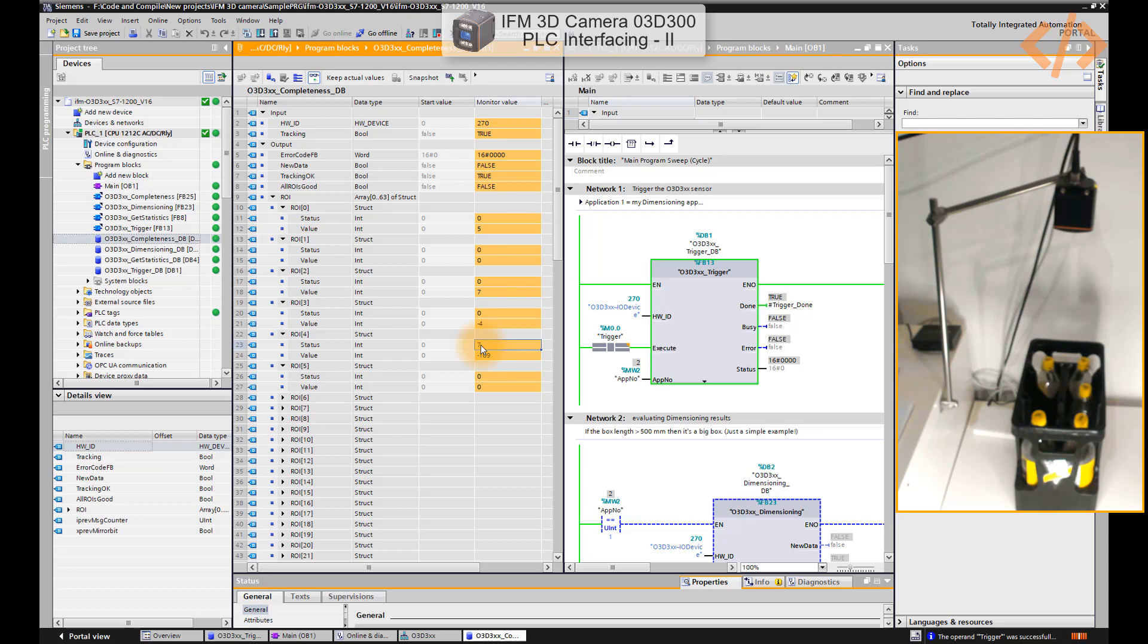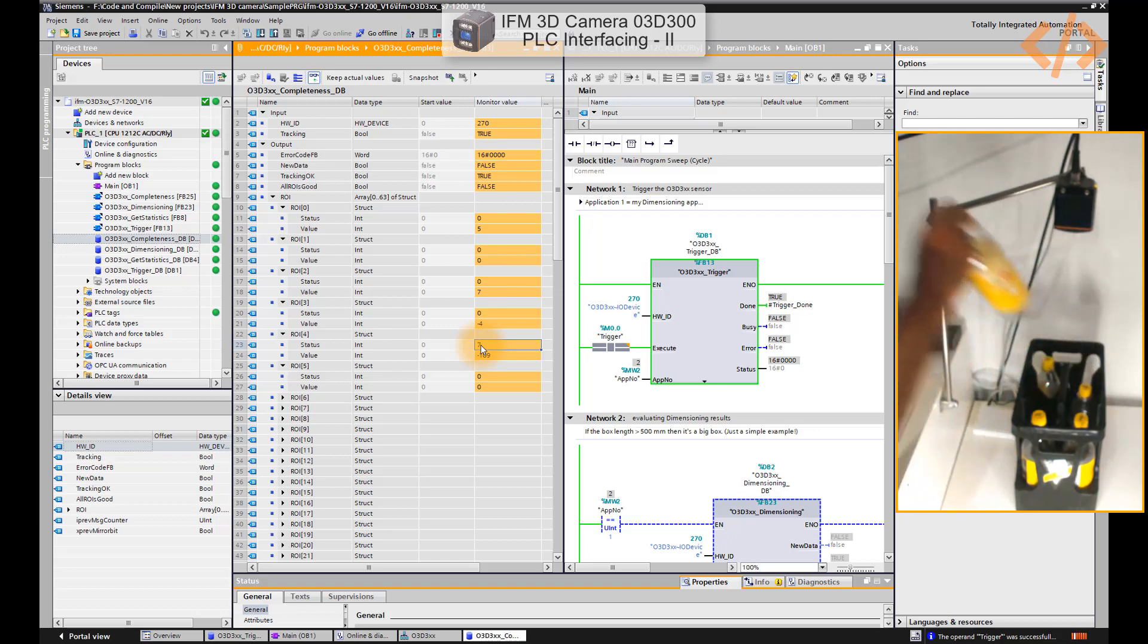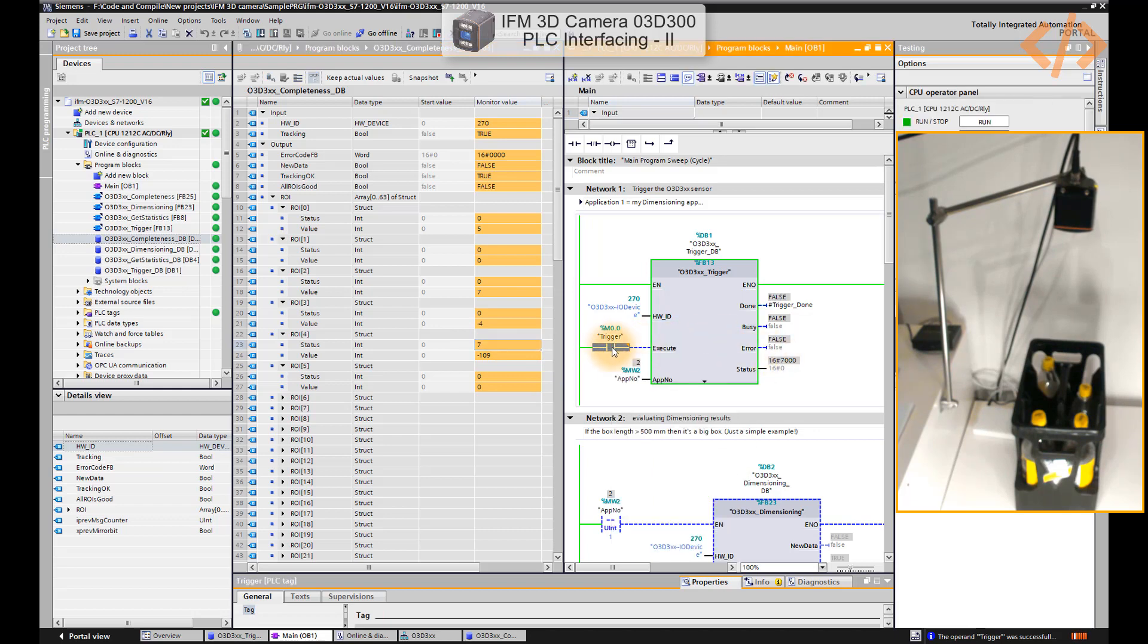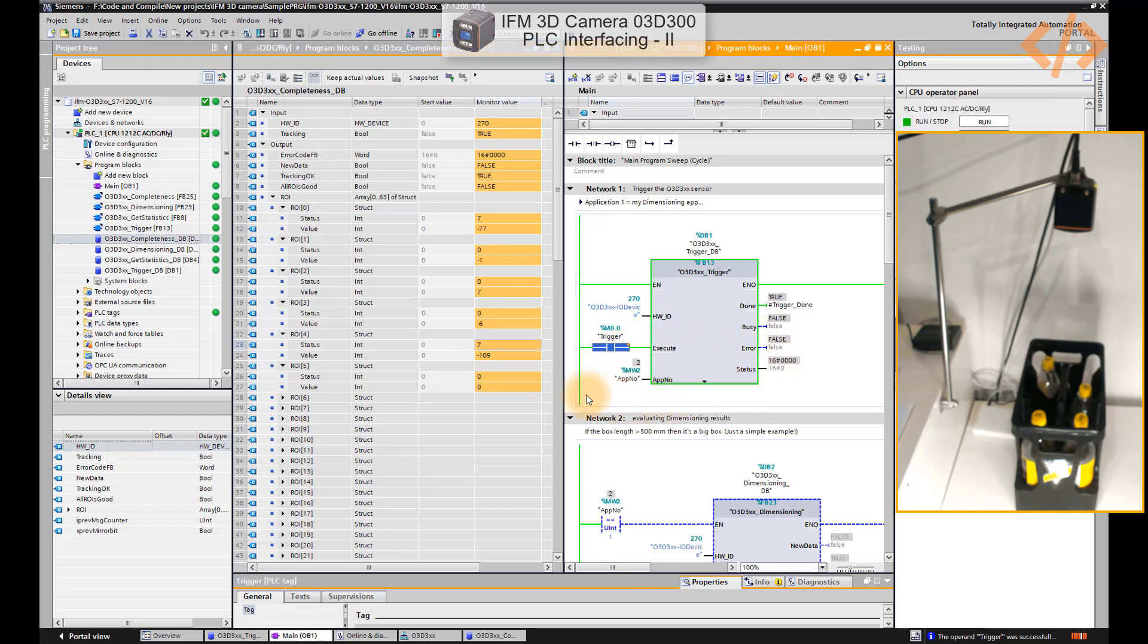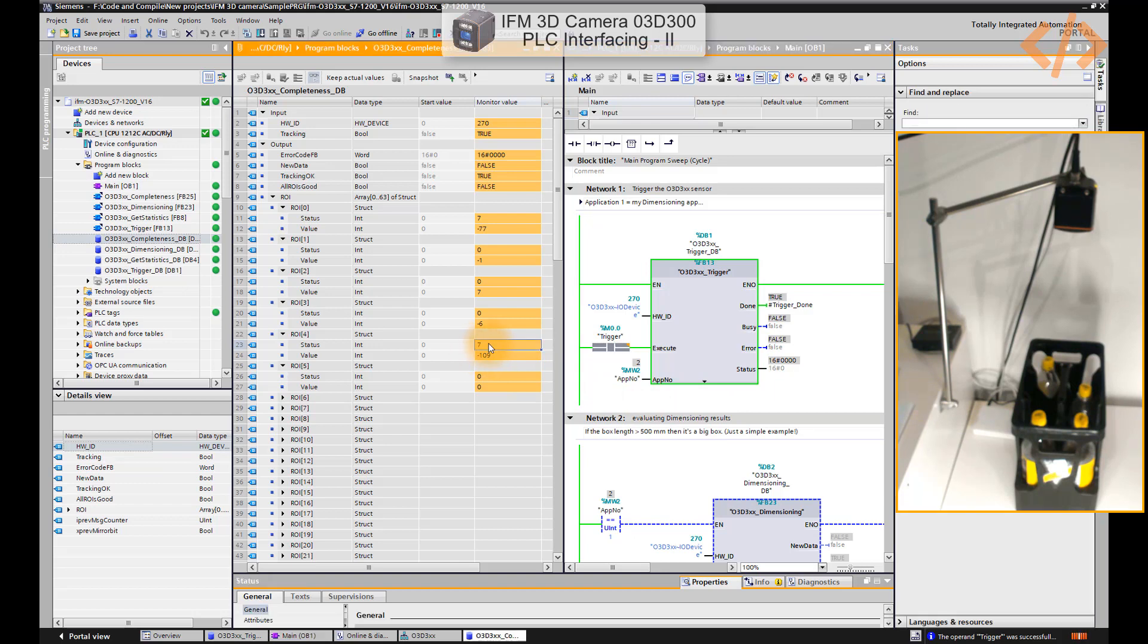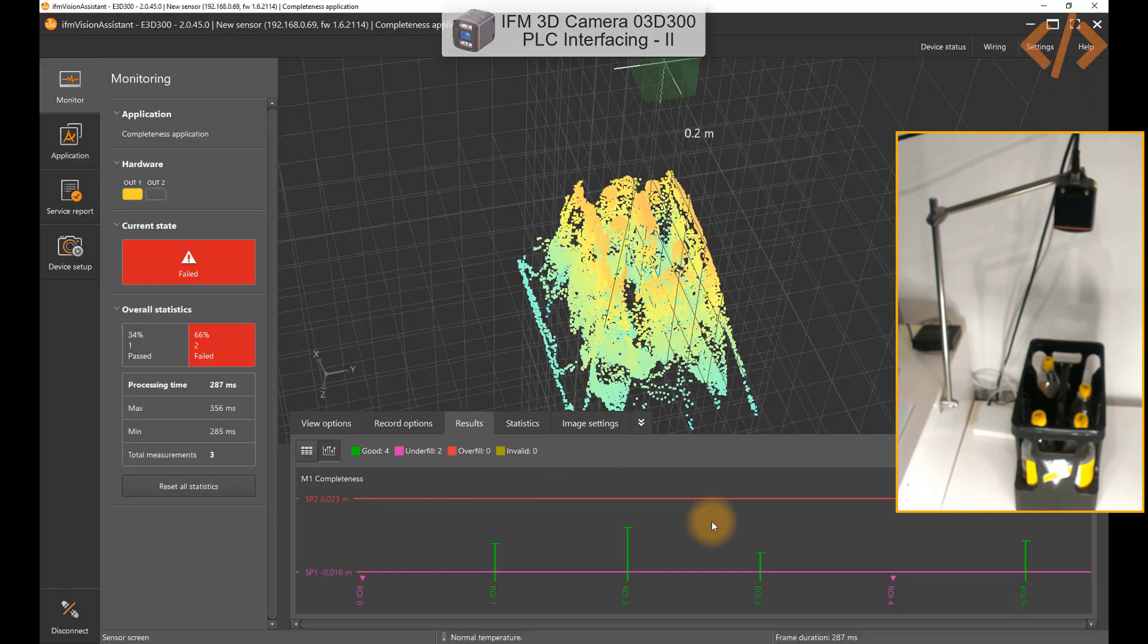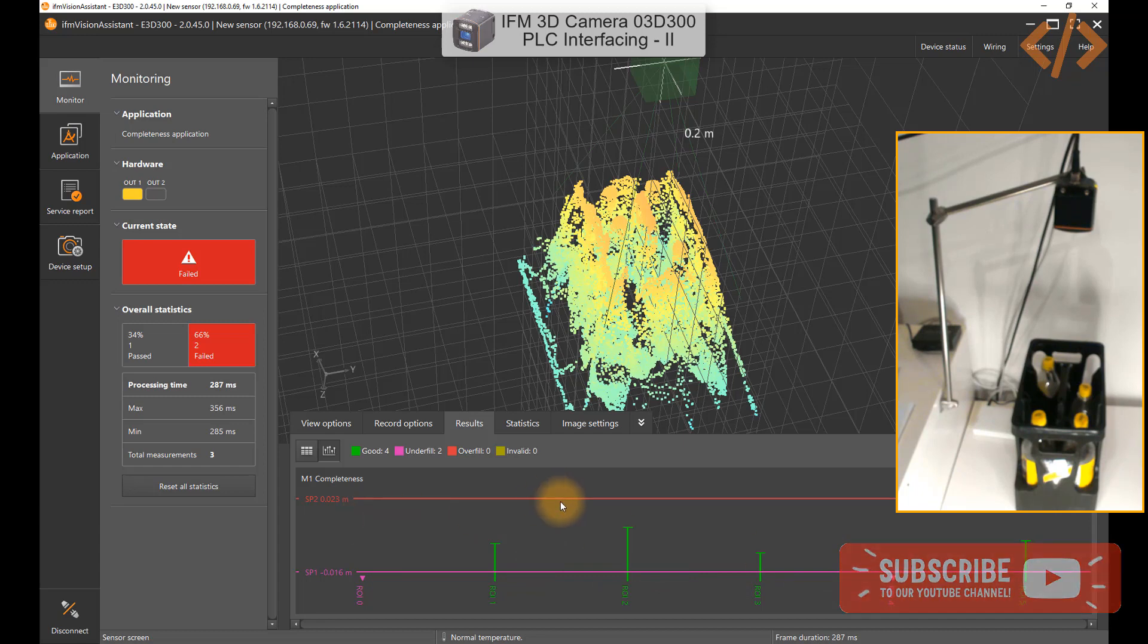Let's take out one more bottle to see the results. Now I'm going to trigger it again, so let's modify to 0 and modify to 1. In this case you see status 7 here and status 7 here, so ROI 0 and ROI 4 are underfill. We can verify that from here.